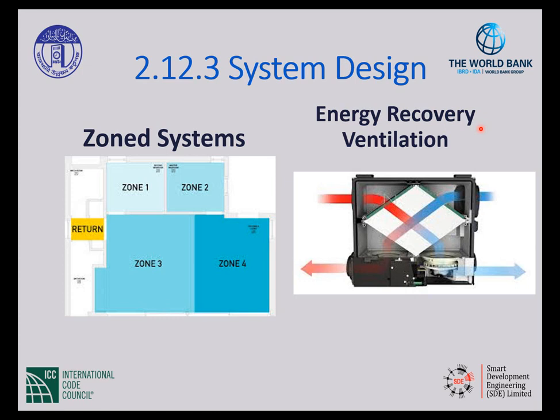And so what an ERV does is it brings that air in from outside, whatever temperature it is. If it's hot air, it takes it across the heat exchanger, pulls the heat off and delivers colder air into the building. So now my air conditioner doesn't have to work so hard. In the winter, it takes that cold air from outside, runs it across the heat exchanger, picks up warm air, adds it to it, and brings it into the building. So you're tempering the air that comes into the building a little bit more and don't have this huge change from outside temperature to inside temperature that your mechanical system has to make up.